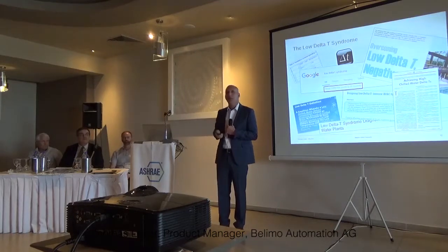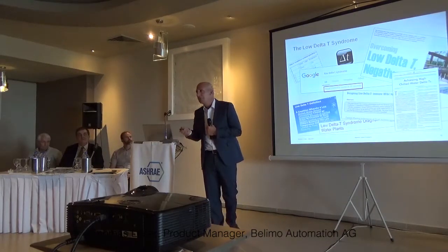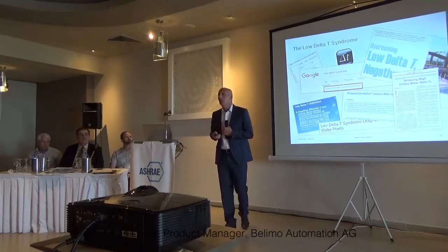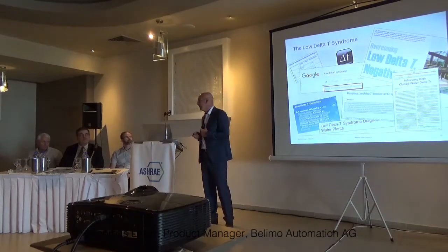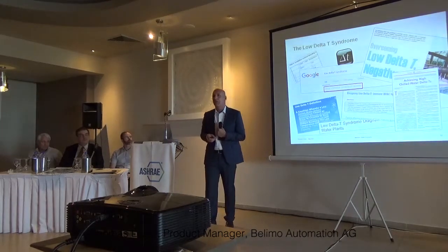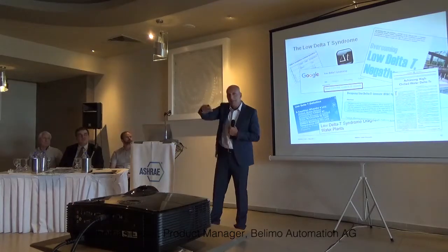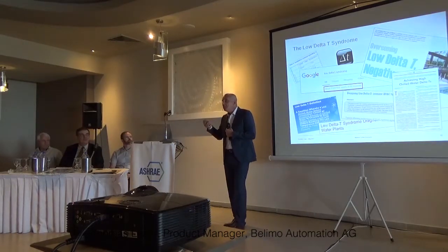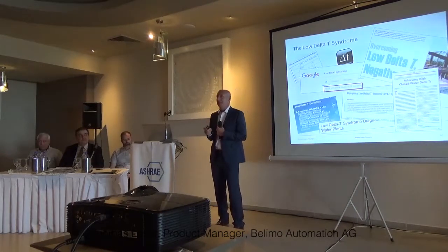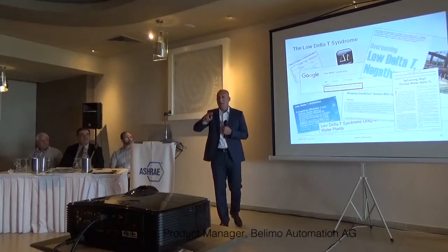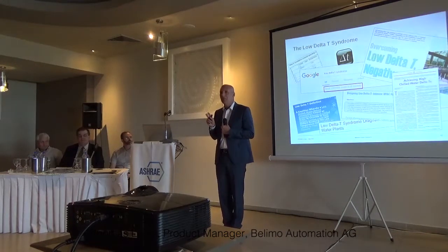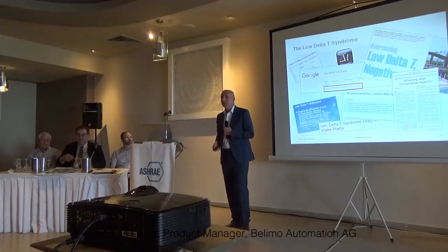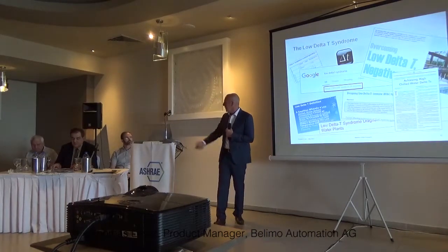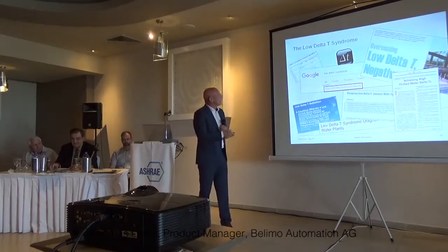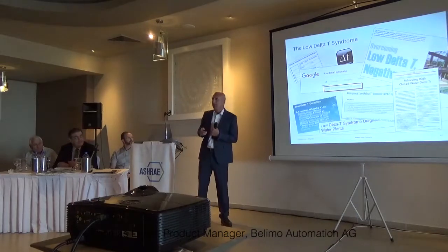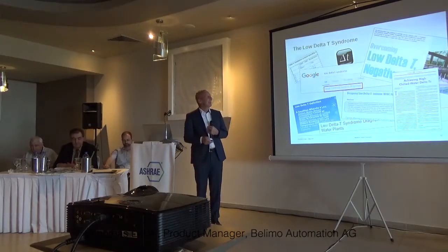Dubai, Middle East, the second biggest supplier of district cooling, is only able to sell 70% of its capacity because of the low delta T problems that are created in the not very well set up buildings, let me say it like this. But imagine, second biggest in Dubai, only 70% of the capacity can be sold. The rest, by the way, is charged to the tenants. So they try to get the money back from behind. But this is a thing that we need to work on. This is something that is critical.